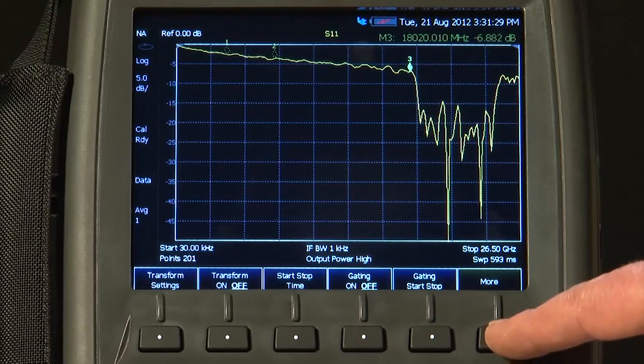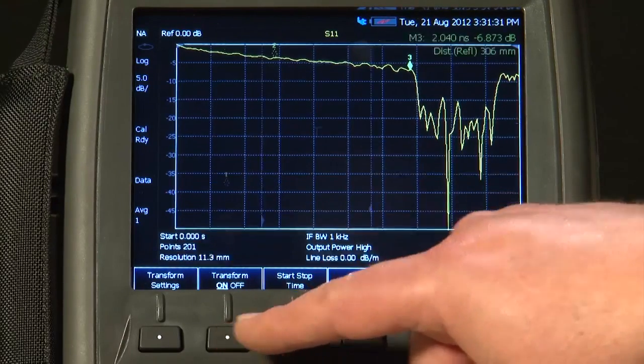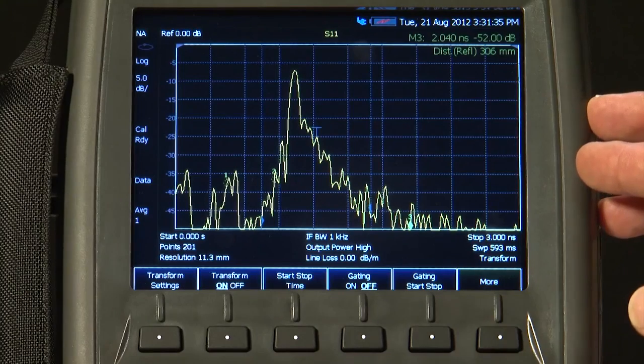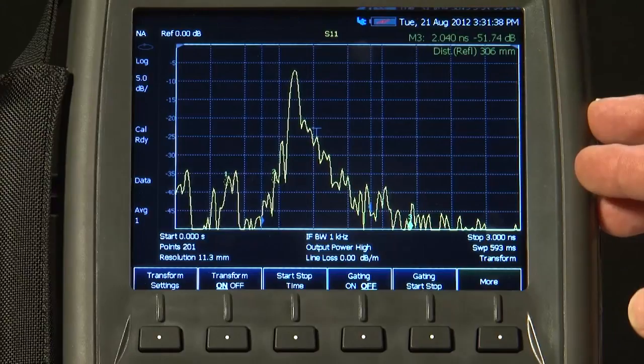So I'll press Meas Setup, Transform and Transform On. And the FieldFox is now performing an inverse Fourier transform of the return loss trace. We are still measuring return loss on the Y axis in dB.